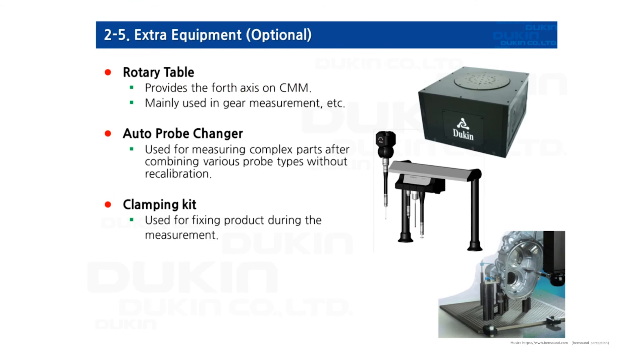Extra equipment is not mandatory, but it is quite useful to have installed on your CMM. A rotary table provides a fourth axis on the CMM. An auto probe changer allows using multiple probes at once without having to calibrate them each time. And a clamping kit is also very useful equipment for fixing complicated shaped parts.